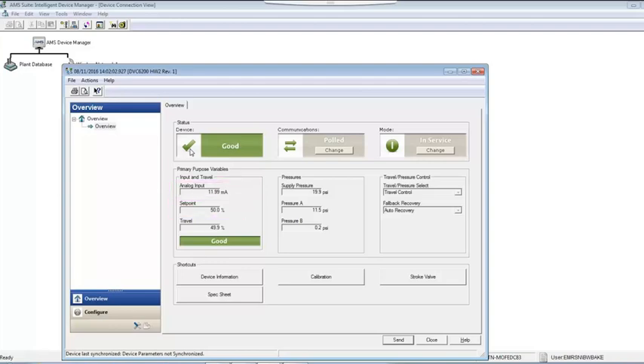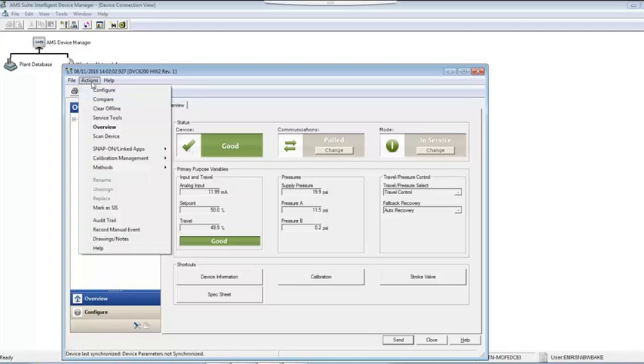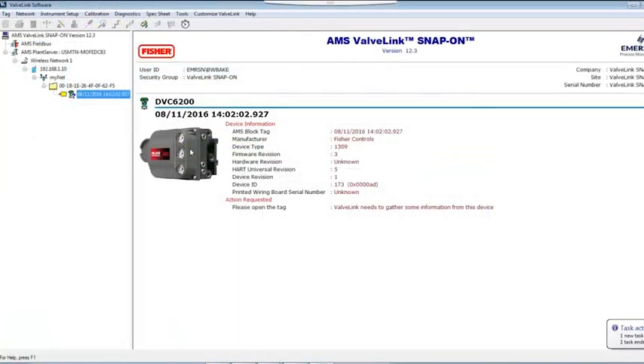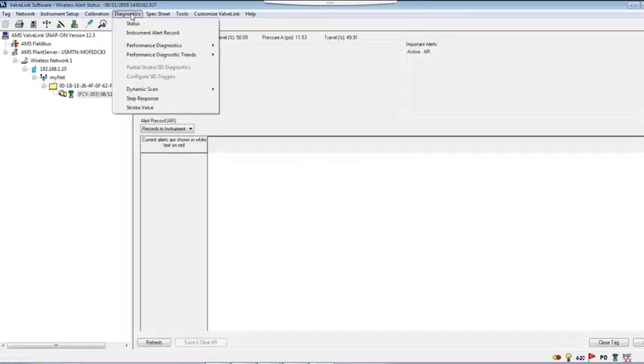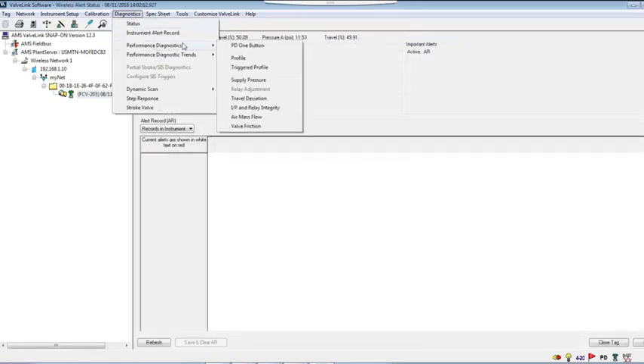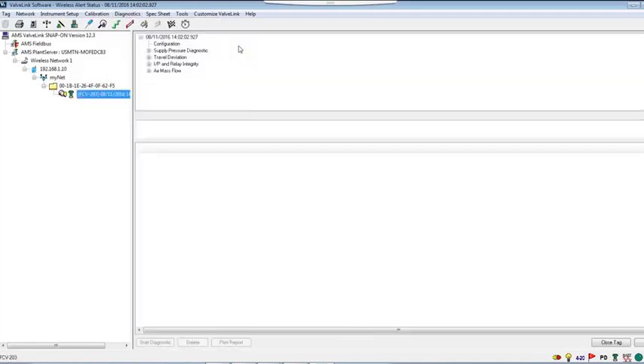a host of alerts. This information would be unavailable if left stranded, but now it can be mapped back to the control system through Modbus or OPC to perhaps trend or archive. Connecting the DVC 6200 wirelessly will also allow for remote diagnostic capabilities using AMS ValveLink snap-on. You'll be able to perform both online and offline diagnostics. Let's start a PD one-button test to see if there are any issues with our current setup.